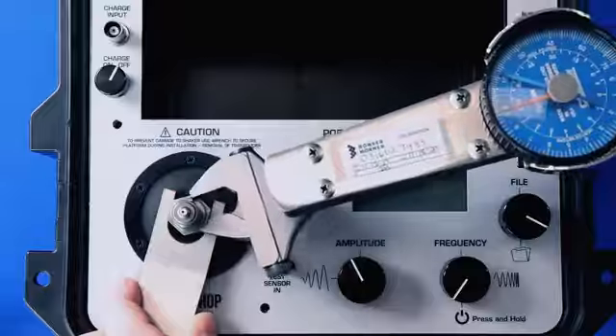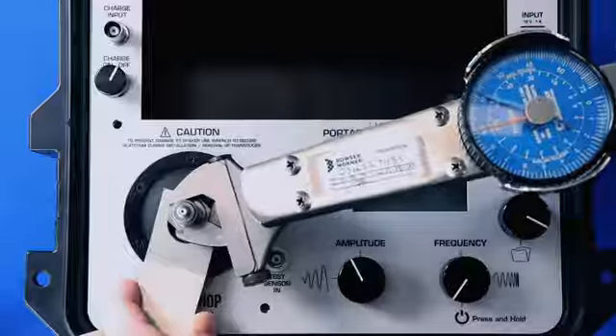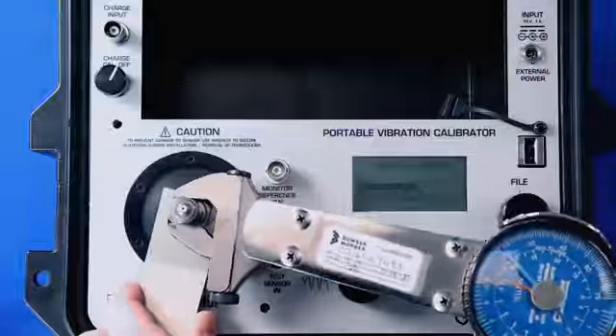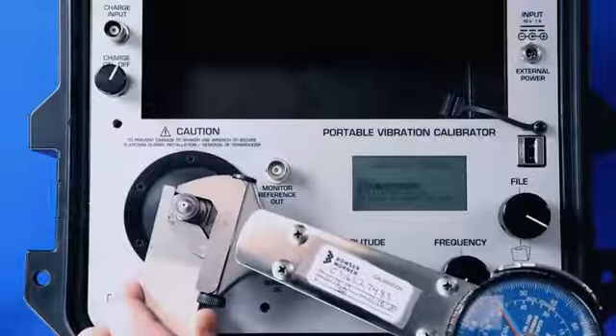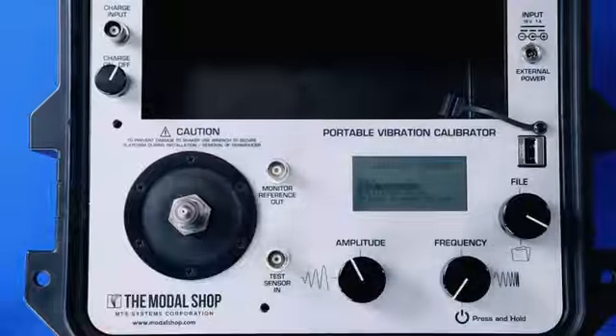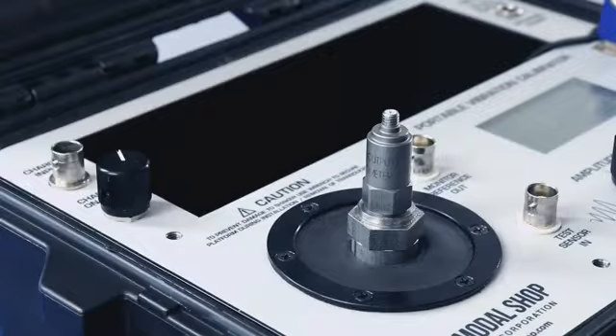Then we use the supplied wrench to secure the shaker's armature, and then we use a torque wrench to apply the proper torque for the calibration of this transducer, and it should be 15 inch-pounds per the manual. Anything from 10 to 20 inch-pounds is fine for the 357B04. Next step is to connect our cable.